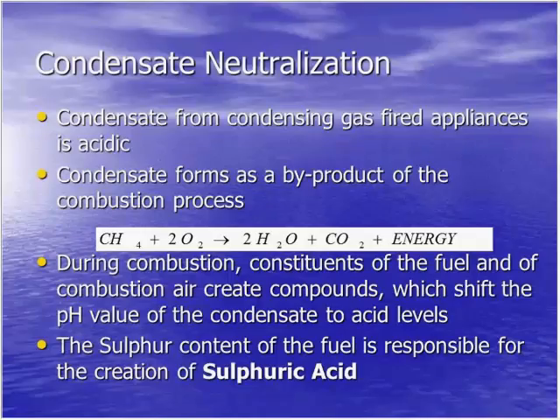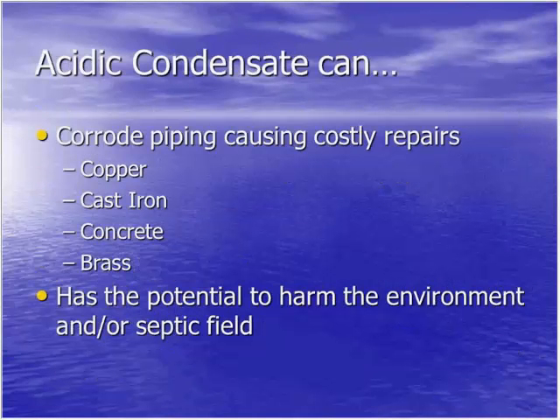An acidic condensate can corrode piping and cause costly repairs in copper, cast iron, concrete, brass components, pretty much anything but plastic. It also has the potential to harm the environment and or the septic field. Septic fields require certain things in order to culture that bacteria and break down those solids and whatnot. So if you've got a lot of condensate dumping into that, it can bring your pH into a range where it's not good for your septic field.